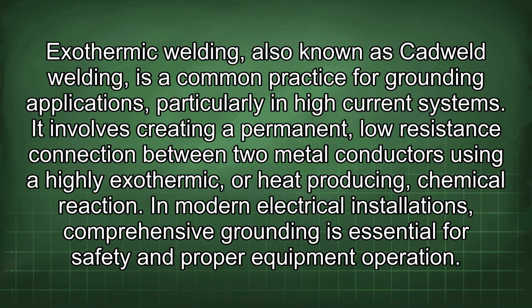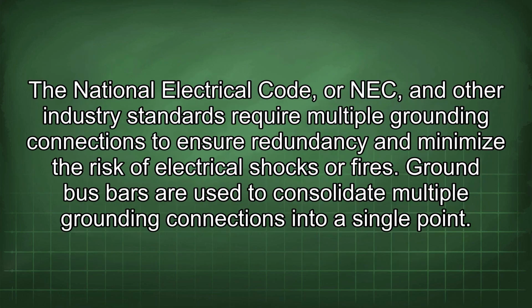Exothermic welding, also known as Cadweld welding, is a common practice for grounding applications, particularly in high current systems. It involves creating a permanent low-resistance connection between two metal conductors using a highly exothermic or heat-producing chemical reaction. In modern electrical installations, comprehensive grounding is essential for safety and proper equipment operation. The National Electrical Code, or NEC, and other industry standards require multiple grounding connections to ensure redundancy and minimize the risk of electrical shocks or fires.